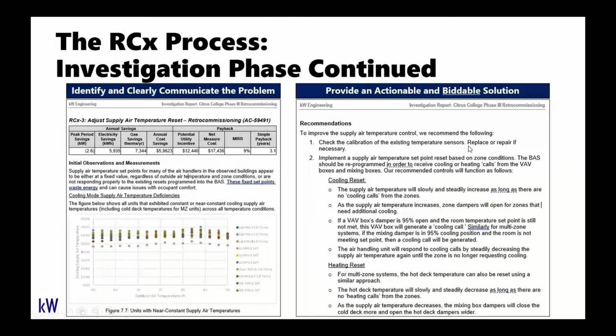So one thing we really tried to focus on with this effort was to lay out step-by-step what's required for the project, so that the controls contractor or mechanical provider, whoever is actually executing the work, in this case Climatech, the control contractor, can have a very specific step-by-step process. Check the calibration of the sensors, repair if needed, and implement the specific sequence based on various inputs and outputs from the control system. This gives us a pathway to the bid and also a good reference to go back to when bids come in and we're comparing different solutions. We can make sure that everybody is providing the same services and adhering to a specific scope that's been laid out.